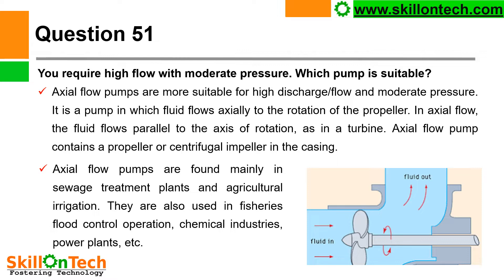Question 51: You require high flow with moderate pressure — which pump is suitable? You can see a picture of an axial flow pump. Axial flow pumps are more suitable for high discharge, high flow, and moderate pressure. It is a pump in which fluid flows axially to the rotation of the impeller — the fluid flows parallel to the axis of rotation, as in a turbine. Axial flow pumps contain a propeller or centrifugal impeller in the casing, and are found mainly in sewage treatment plants, agriculture irrigation, fisheries, flood control, chemical industries, power plants, etc.